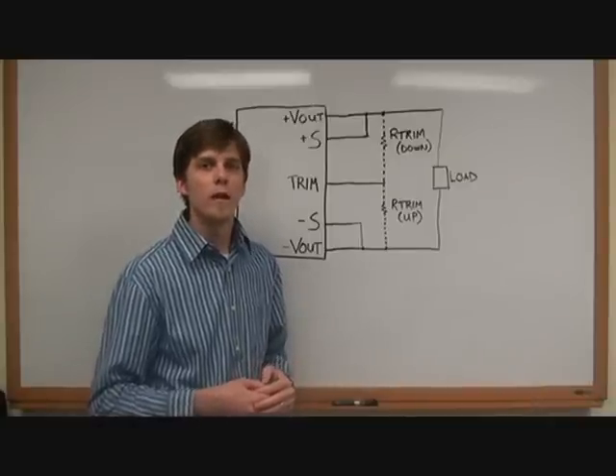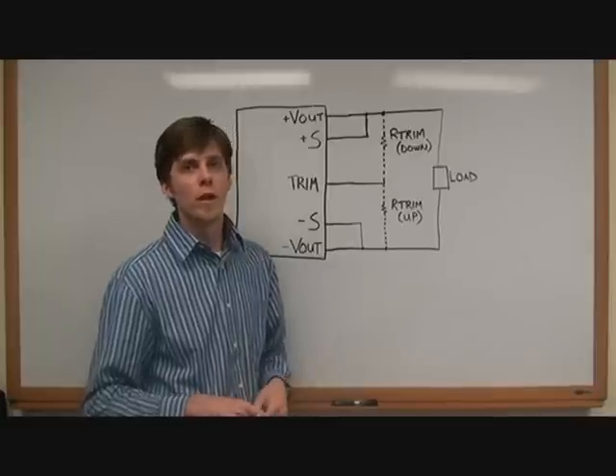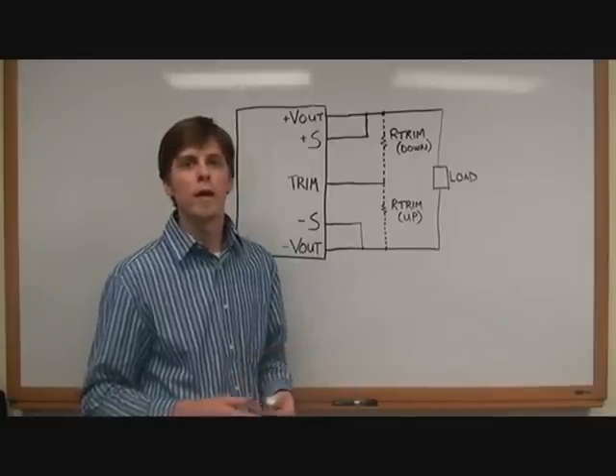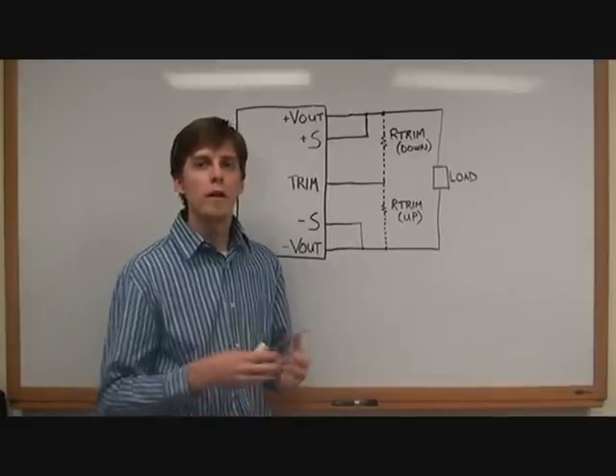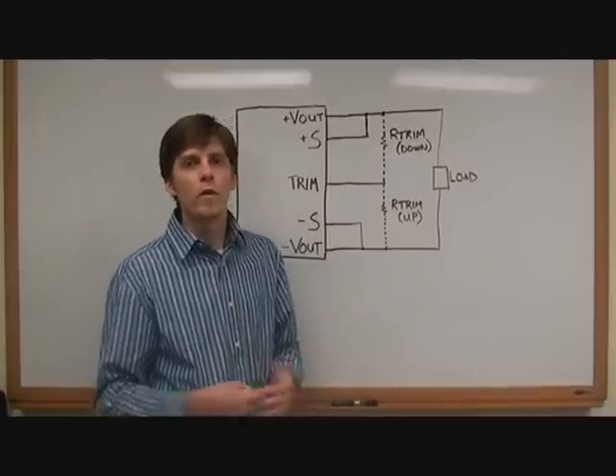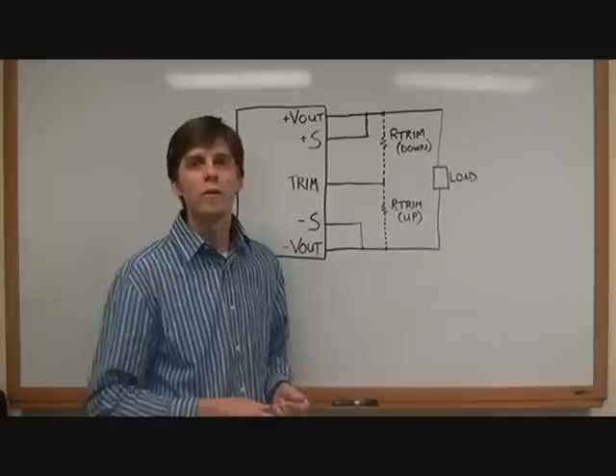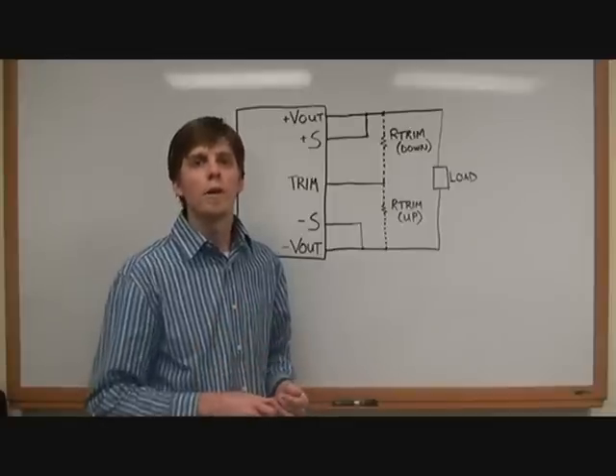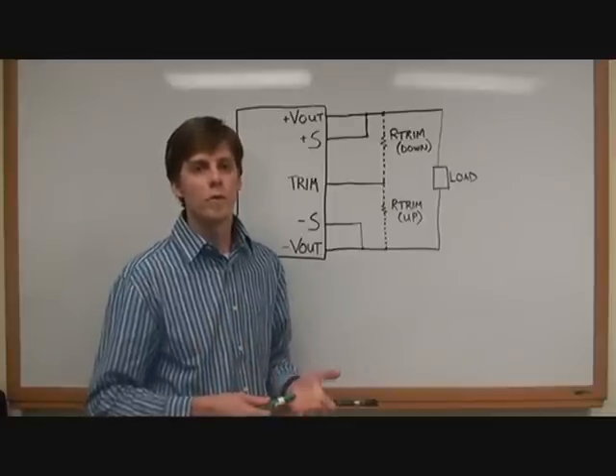Quite a few of our converter product lines, you can trim the output voltage, either adjust it up or down. So if you need a non-standard output voltage, let's say you need 10 volts, we make 12 volt converters. Well, with one resistor, you can operate that 12 volt converter at 10 volts.